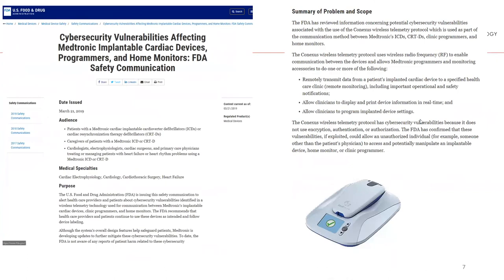Another example regarding cardiac devices — a defibrillator from Medtronic. The major issue here is that Medtronic was using their own proprietary wireless protocol which had no protection, no encryption — no encryption, authentication, or authorization. Basically, anybody listening to this communication on the correct frequency channel can get the data. In fact, they can hijack it and perhaps manipulate that data as well. This is your heart — cardiac devices. This is a very, very serious vulnerability.